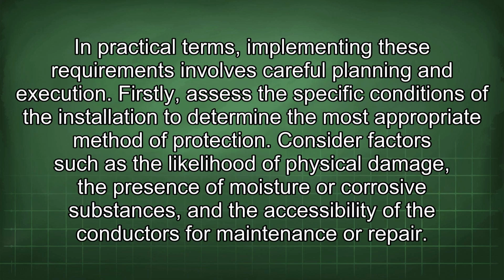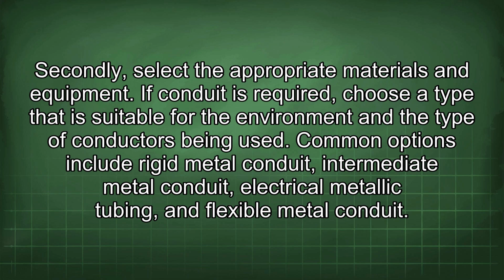In practical terms, implementing these requirements involves careful planning and execution. Firstly, assess the specific conditions of the installation to determine the most appropriate method of protection. Consider factors such as the likelihood of physical damage, the presence of moisture or corrosive substances, and the accessibility of the conductors for maintenance or repair. Secondly, select the appropriate materials and equipment. If conduit is required, choose a type that is suitable for the environment and the type of conductors being used. Common options include rigid metal conduit, intermediate metal conduit, electrical metallic tubing, and flexible metal conduit.